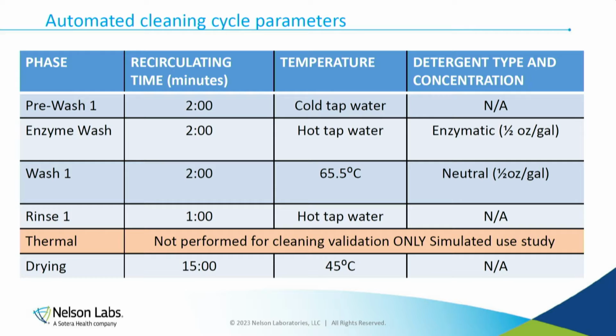And I've outlined the thermal cycle here because that is not part of the cleaning. It happens in the hospital, and it is in your IFU, but we're not going to use that. We're going to omit it and validate the rest of it, because that is now a disinfection step. You just added a disinfection step to the cleaning validation, and you have to assess those separately. Disinfection separate, cleaning separate, because the endpoints are different. And so for simulated use cycles, like we talked about, those are included because that is happening in the hospital. But in real life, in the validation world, we have to break them apart and validate them accordingly.